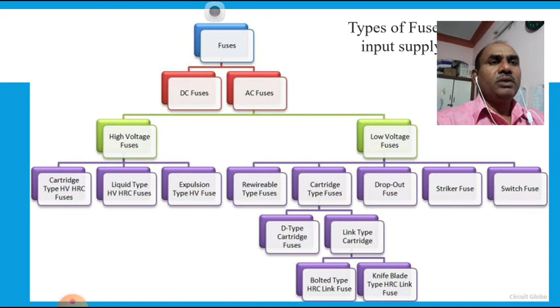Now let us see the DC fuse. The DC fuse opens or breaks the circuit when excessive current flows through it. It is the normal operation of the fuse. You can see a DC fuse on the slide. The only difficulty with the DC fuse is that the arc produced by the direct current is very difficult to extinguish, because there is no zero current in the circuit. In case of AC, we have a 50 Hz frequency in India. That means every second the positive and negative waves occur 50 times, so the current touches zero magnitude 100 times in 1 second.